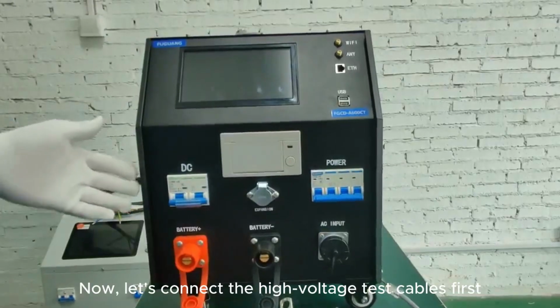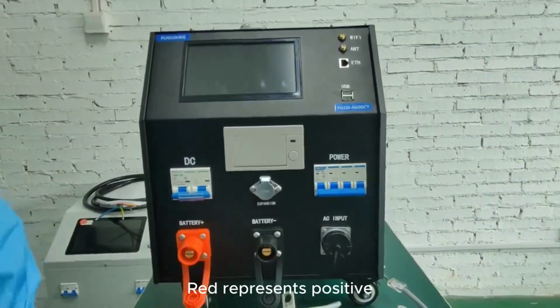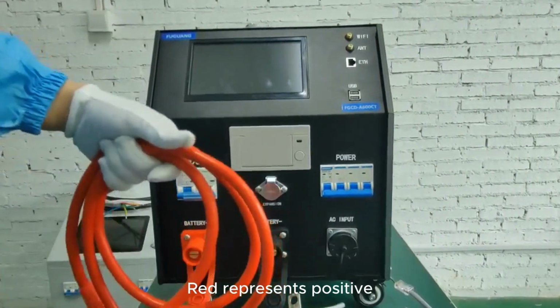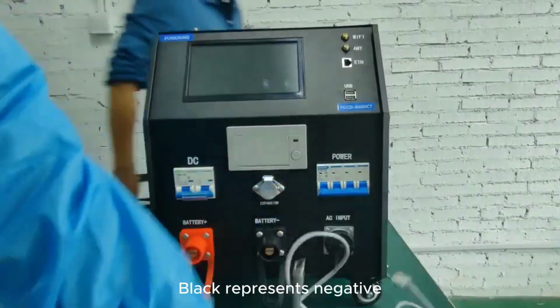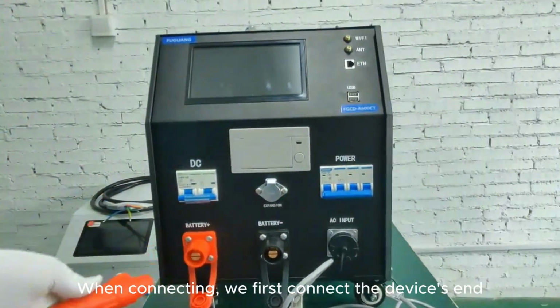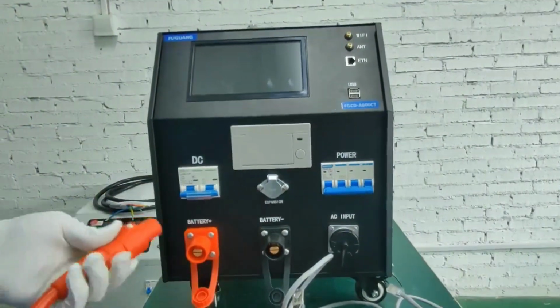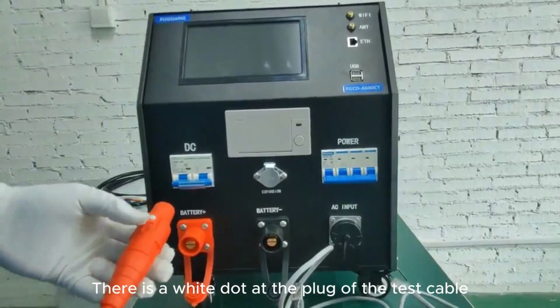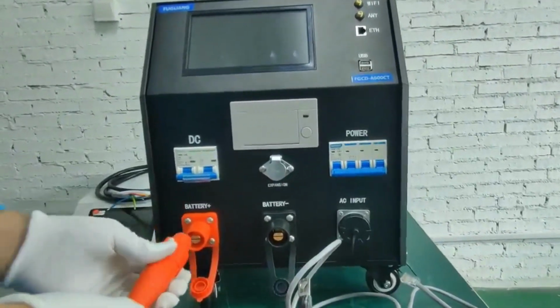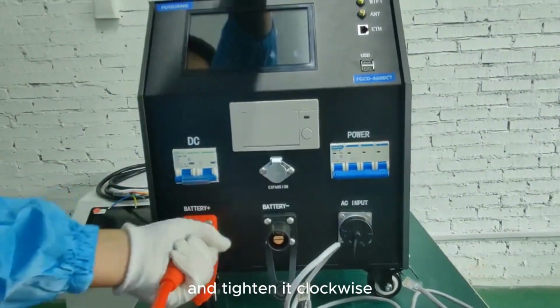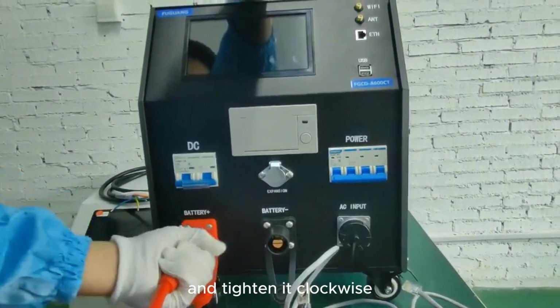Now, let's connect the high voltage test cables first. Red represents positive. Black represents negative. When connecting, we first connect the device's end. There is a white dot at the plug of the test cable. The white dot faces up. Then plug it in the positive port and tighten it clockwise.